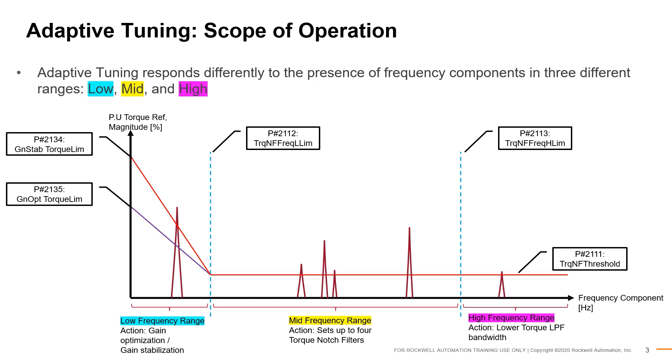In the high frequency range, the available action is the detuning of the torque reference low pass filter. The presence of high frequency components often hint at a system entering instability, and the lowering of the torque reference low pass filter bandwidth serves as a stop gap measure to prevent the system from becoming unstable. This prevents imminent faults resulting from unstable operating conditions, allowing for uninterrupted system runtime.